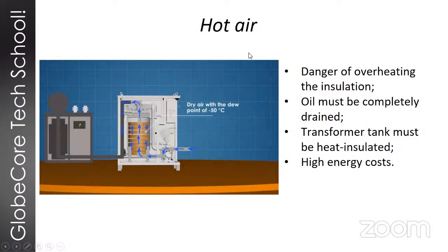So one of the perhaps simplest methods of drying solid insulation is hot air purging. What it does is basically blowing hot air at a temperature of 100 to 110 degrees Celsius through the transformer. However, the method has some limitations and drawbacks. One of them is the high probability of overheating the solid insulation locally or entirely. Also, this method only works if you pump all the oil from the transformer. And since there is a significant degree of heat loss through the transformer tank, this process is actually quite expensive in terms of electricity or energy. It's not very energy efficient.